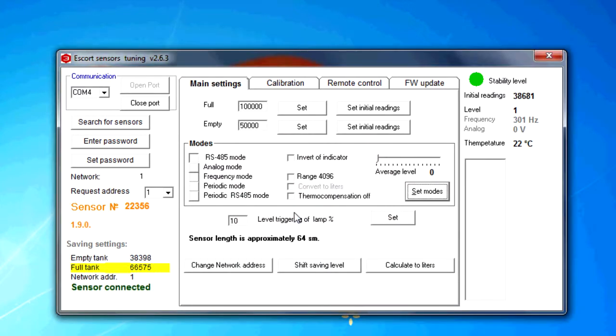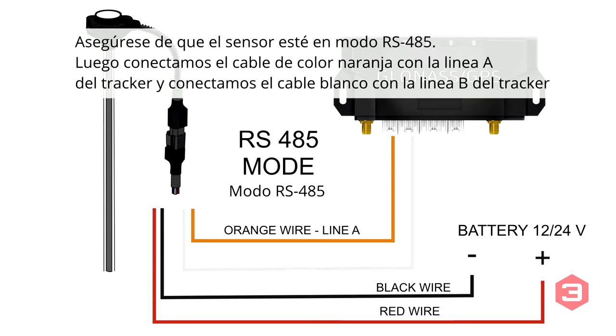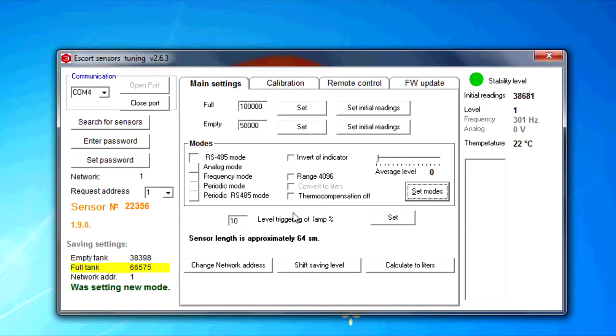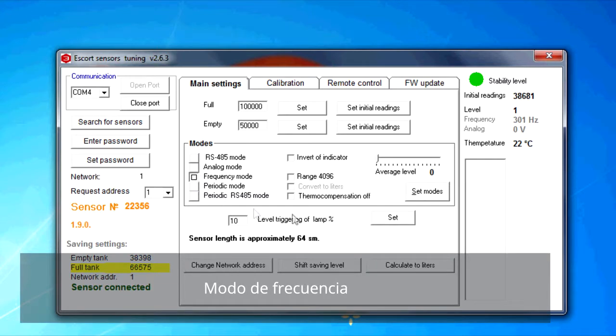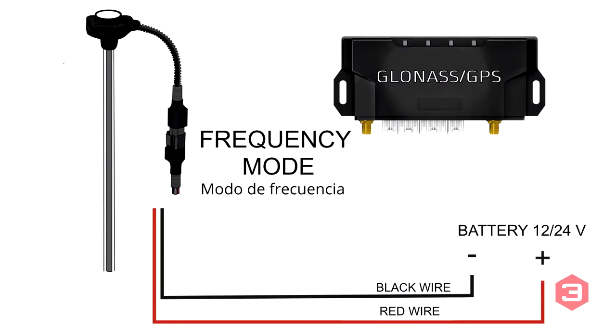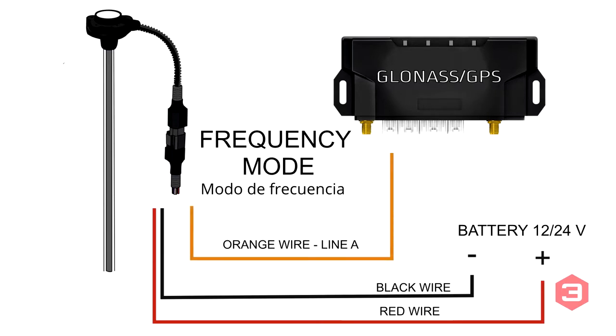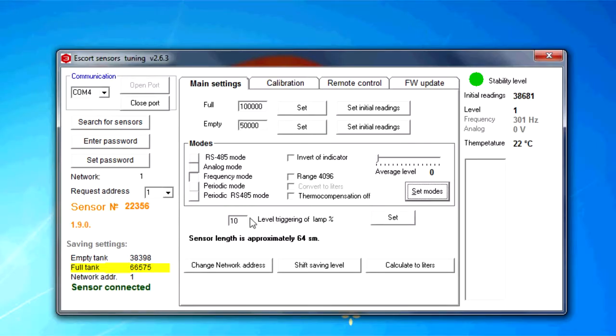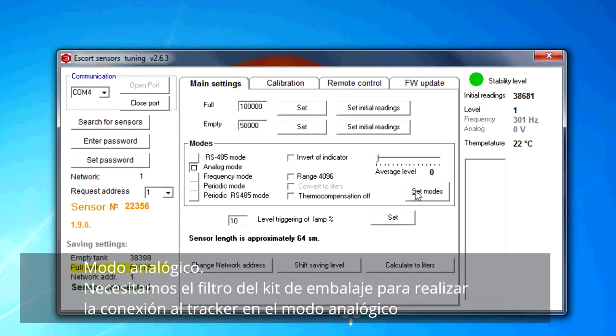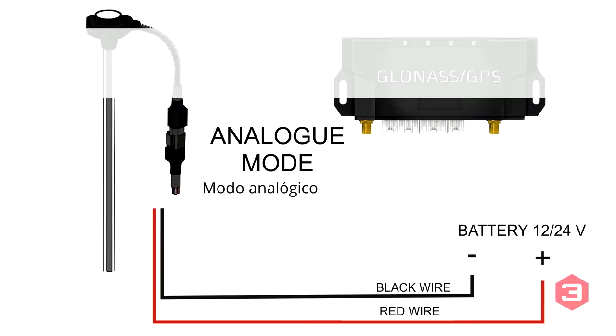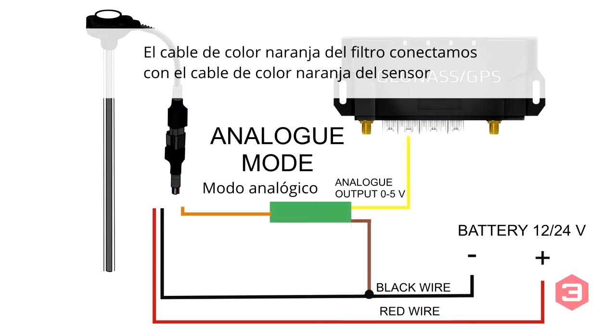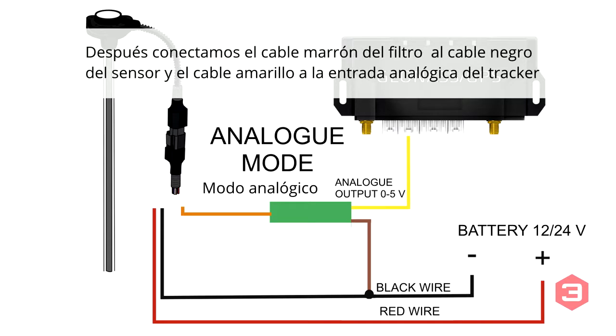Confirm that the sensor is in the RS485 mode and then connect the orange wire to the line A of the terminal and the white wire to the line B. Frequency mode. In frequency mode, only the orange wire is connected to the terminal input. For some terminals, a pull-up resistor is required. For this purpose, it is better to use a 1 kilo-ohm resistor. Analog mode. You will need a filter from the installation kit to connect the terminal in this mode. Orange wire of the filter is connected to orange wire of the sensor. Brown wire of the filter is connected to black wire of the sensor, and yellow wire is connected to the analog input of the terminal.